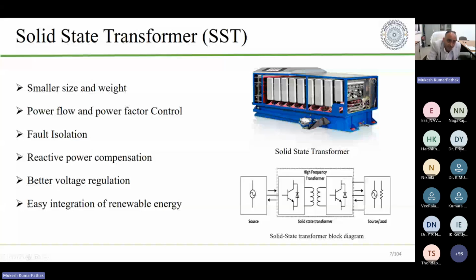Now the reactive power compensation, which is required with large loads where you have a low power factor, that is also additional investment. In the case of a solid state transformer, you can provide this compensation through control of the power converters. So the additional reactive power compensators that we need to install when the power factor is poor are not required. So the solid state transformer looks like a complete package.